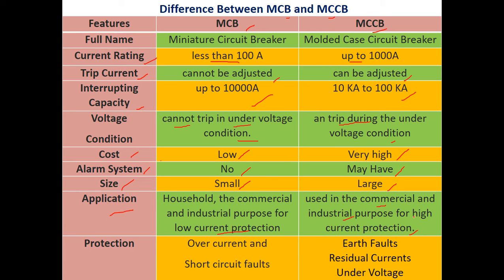In terms of protection, MCB protects against overcurrent and short circuit faults. MCCB also provides protection against overcurrent and short circuit; however, we prefer MCCB because it additionally protects against earth faults, residual currents, and under-voltage conditions, which are not offered by the MCB.